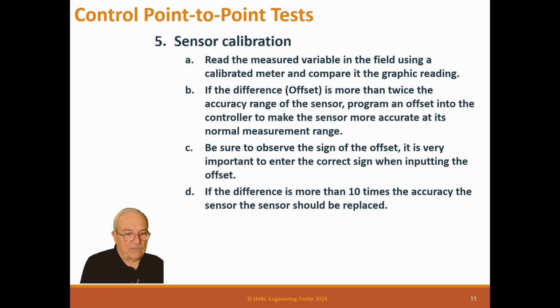Now, a lot of contractors will tell you, well, the temperature sensors are factory calibrated. We don't need to calibrate them. It depends on the type of sensor it is. If it's a thermistor or a Balco or something like that, it's actually a resistive device, so the wire actually affects the temperature reading. So you have to field calibrate them. It's not that the sensor's bad, it's just that we have to calibrate it to what it actually sees in the field. If it's got 150 foot of wire on it, or 50 foot of wire on it, it'll read differently, so you need that. And 10 times accuracy is pretty safe. If it's plus or minus 1, that's 2 degrees, so if it's off by 20 degrees, you need to check what's going on here.